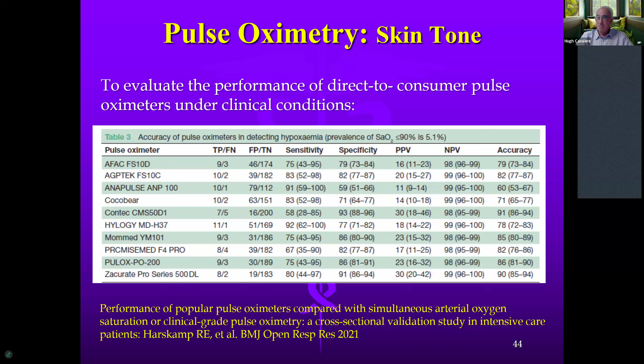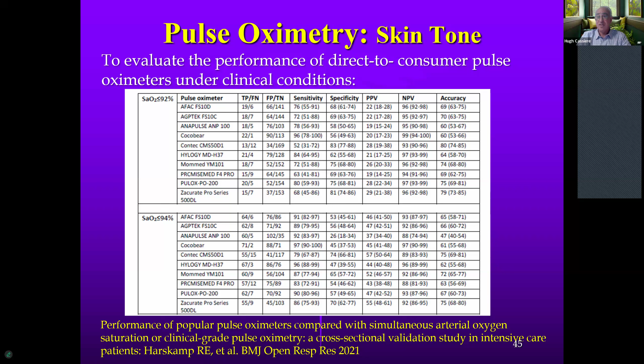This looked at different thresholds. Was it good at picking up O2 sats of less than 92%? Or how about less than 94%? If you take a look at the accuracy numbers, these over-the-counter pulse oximeters were horrible. Some of them were almost like flipping a coin as to whether someone was hypoxic or not. So I beg you, I would not use them clinically. We already have a problem with the quote-unquote best hospital-grade pulse oxes. These take it to a different level. So please don't use these over-the-counter pulse oxes. Unfortunately, a lot of these were used during the pandemic to help manage patients, which is probably one of the reasons why there are such excessive mortality rates in patients with darkly pigmented skin.